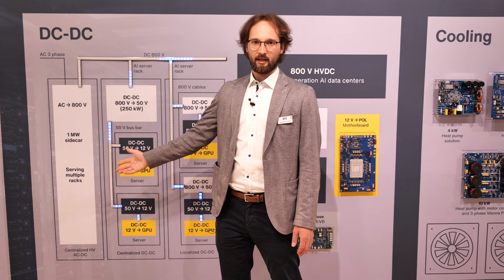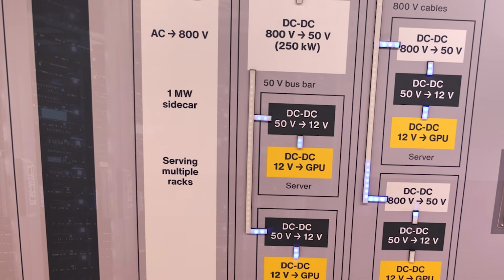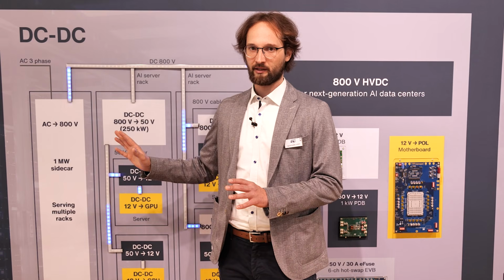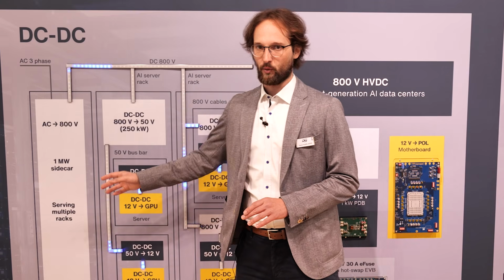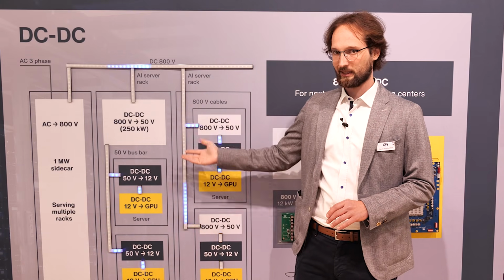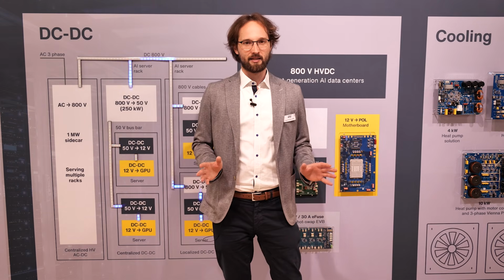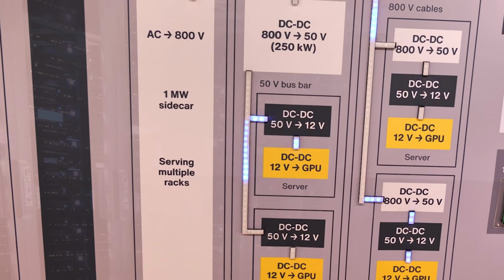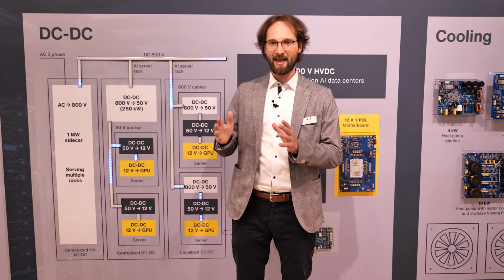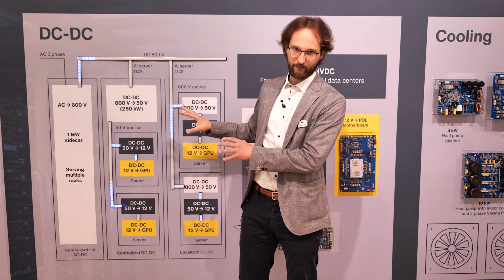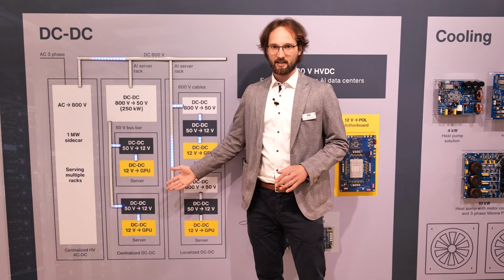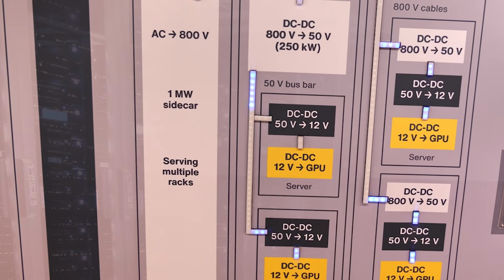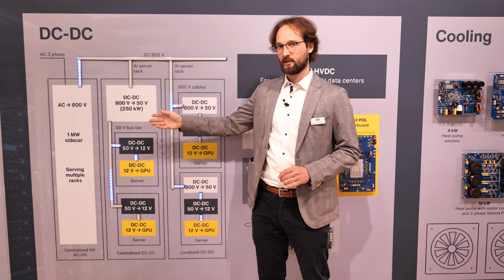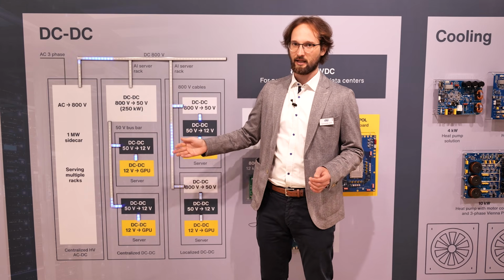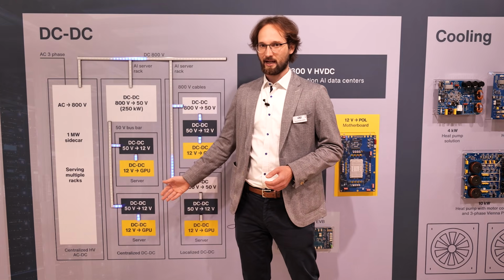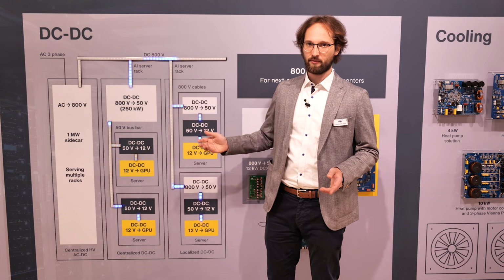The first is the centralized high-voltage AC-DC sidecar, a 1 megawatt converter that takes grid AC to 800-volt DC and serves multiple racks. The argument is that a single high-power converter serving many racks is more efficient than many smaller converters in every rack. The second is a server rack with centralized DC-DC, an 800-volt to 50-volt conversion at 250 kilowatts that feeds a 50-volt bus bar inside the rack. Then each server steps down from there.